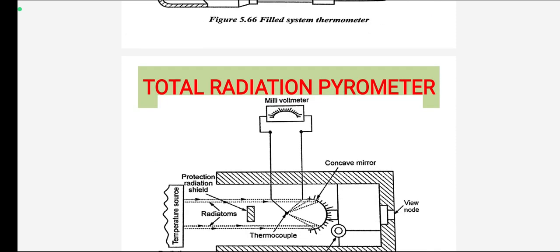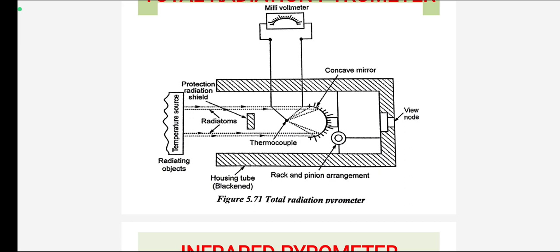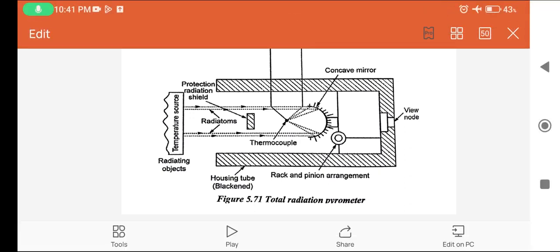And next one, the total radiation pyrometer. The total radiation pyrometer works on the radiation of the temperature source. Here we have the two junctions, hot junction and cold junction. The total radiation pyrometer has the temperature source, protection radiation shield, concave mirror, millivoltmeter and housing tube. The radiation is focused through the protection radiation shield onto the hot junction of the thermocouple. The temperature difference between the hot junction and cold junction is measured by the total radiation pyrometer.